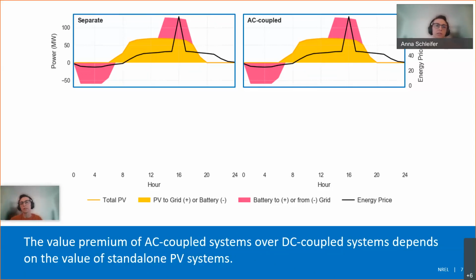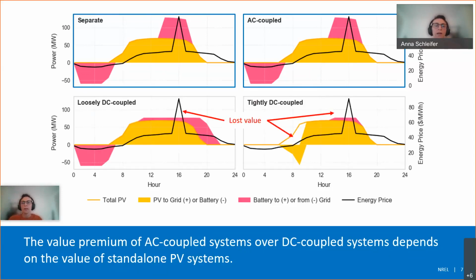And here, because the highest prices occur during daylight hours, the AC coupled system operates the exact same as separate systems, where the battery charges overnight and discharges at the same time that the PV is generating to meet those high price hours. If you compare those to DC coupled systems here on the bottom, in the case of the loosely DC coupled system, you're still charging at night, but now your discharge during the day is limited to the shared inverter capacity. So in both DC coupled cases, you lose some value because the system cannot provide energy at the full PV inverter and battery inverter output.